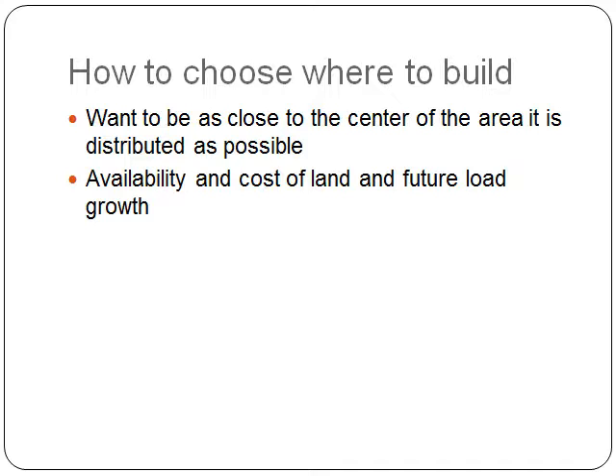How is a substation location chosen? It is most optimal if the substation is built close to the center of the area it distributes, because then you would have the shortest length of feeders needed to reach customers. However, there are other factors to consider, such as the availability and cost of land, as well as future potential load growth of the location it is serving.